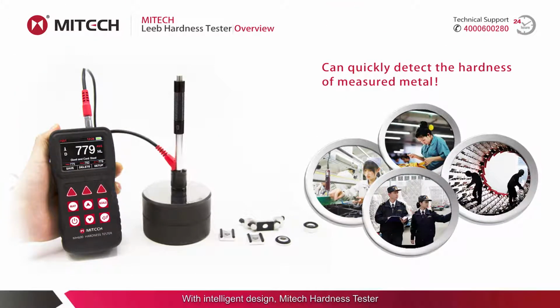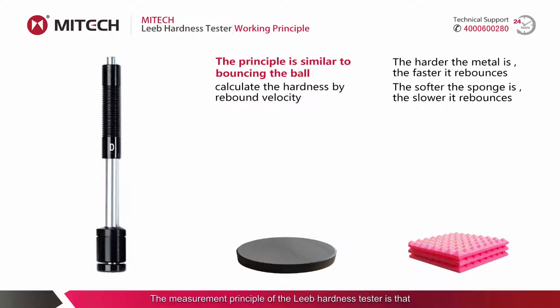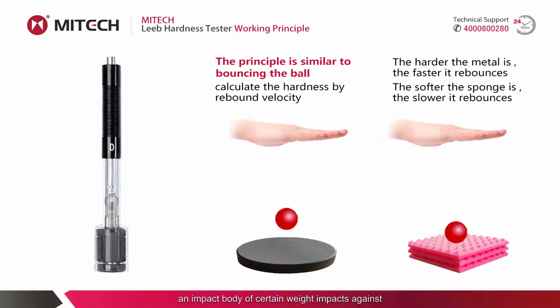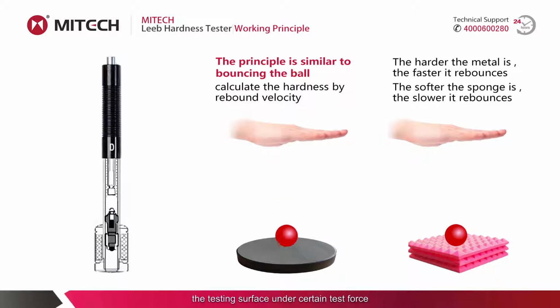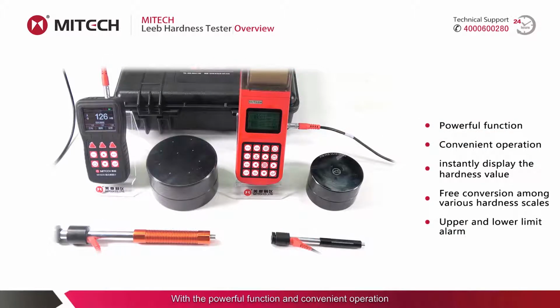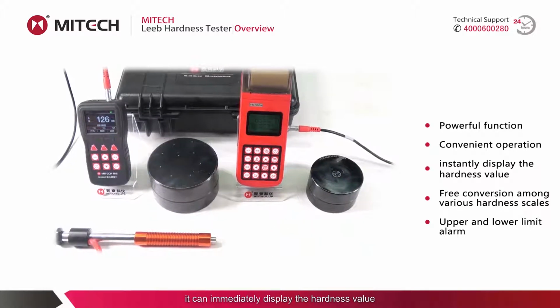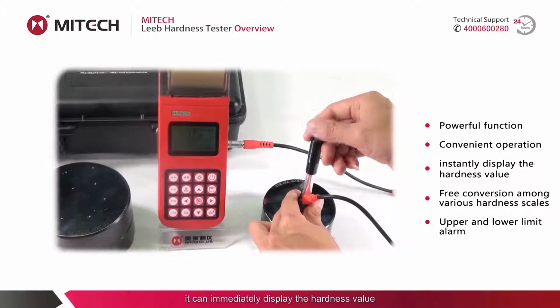With intelligent design, the Mitech hardness tester can test the hardness of metals easily and quickly on site. The measurement principle of the LEEB hardness tester is that an impact body of a certain weight impacts against the testing surface under a certain test force. The hardness value is calculated from the ratio of the rebound speed and the impact velocity at 1 mm from the specimen surface. With a powerful function and convenient operation, it can immediately display the hardness value.